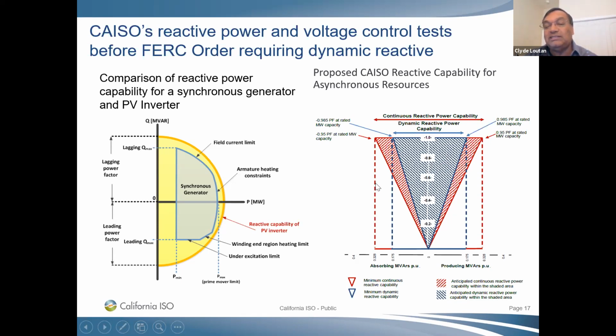Well, as it turns out, when we were doing this test, the results were very, very encouraging. Those two plots that you see, the blue dash line and the red dash line, are what the plant can actually do. So it's a lot better response, and I get into that in my next slide, than what we were expecting. When you look at the plot on the left, you can see for the synchronous resource, this is your voltage capability here, this area right here, because you have a lot of limitations on synchronous resources. But with a PV plant, you can get this semicircle here, which is lagging, leading power factor control. That's a lot better than a conventional resource. So again, this was very encouraging.